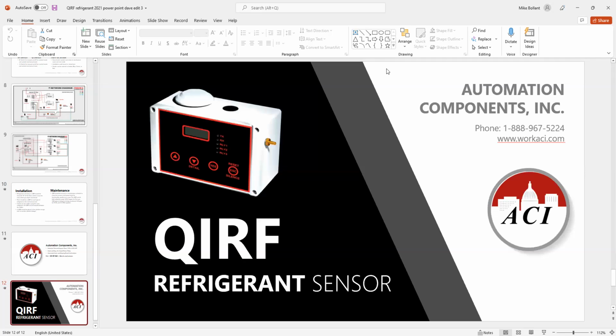Questions on this system, and once again, we'll help you guys lay it out. Questions we'll ask are, what type of Freons are your chillers? What's the mechanical room? Or if you have a mechanical room drawing, send it to us and we'll lay it out for you. We'll ask you the questions: do you need the BACnet option, or is it Modbus coming back to the BAS, or is it standalone? Do you want it inside the room, outside the room? Those are just basic questions that we would ask you guys.